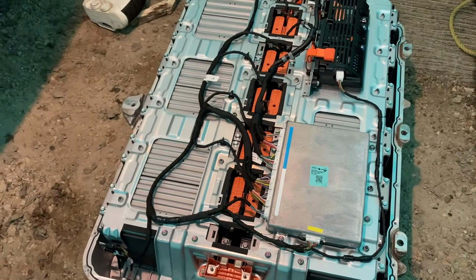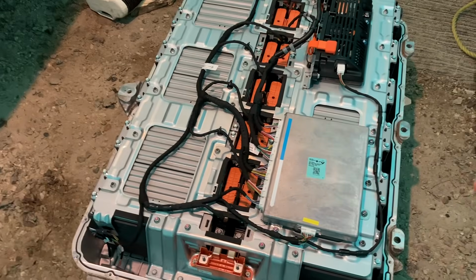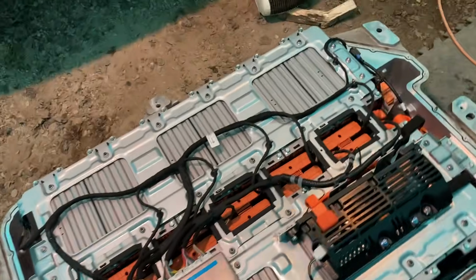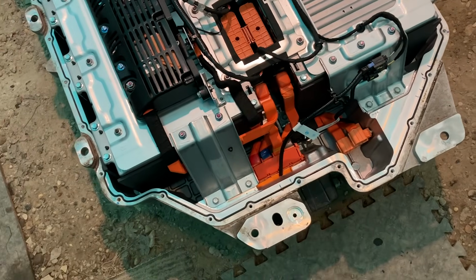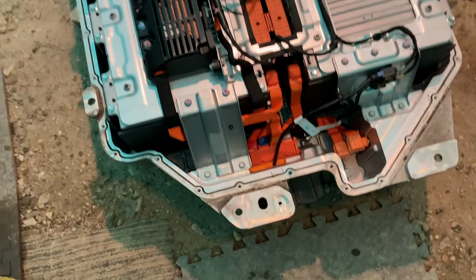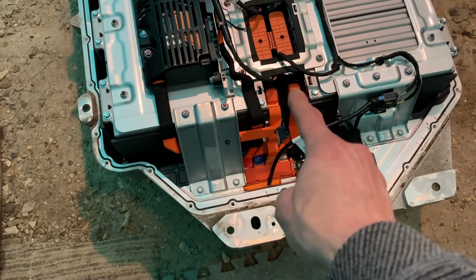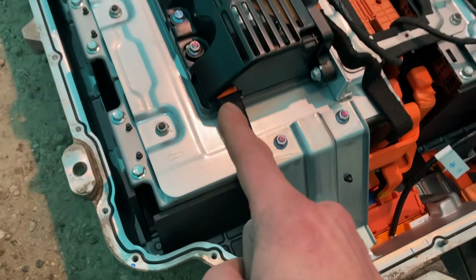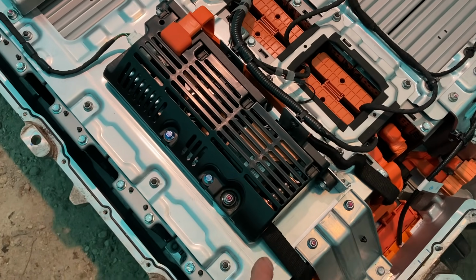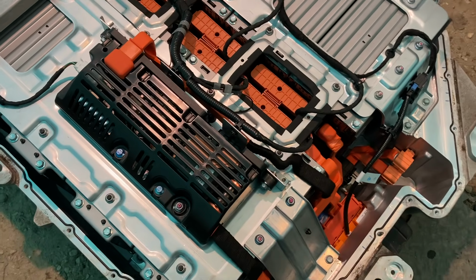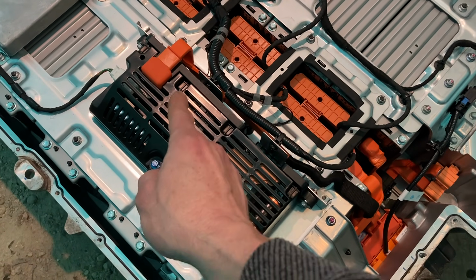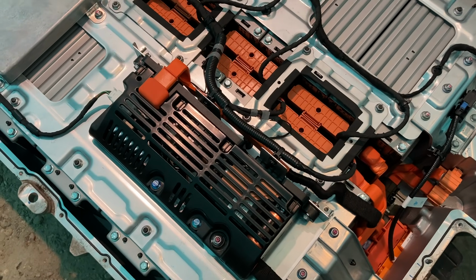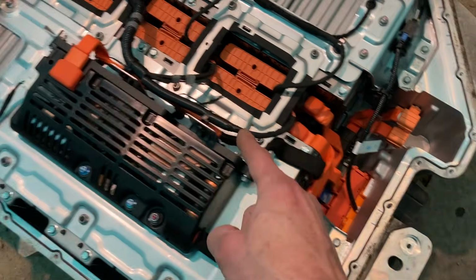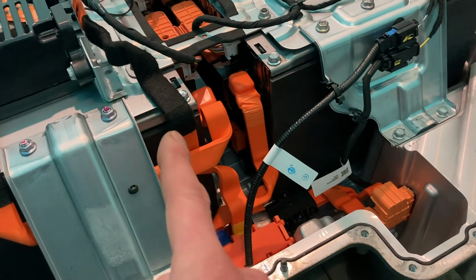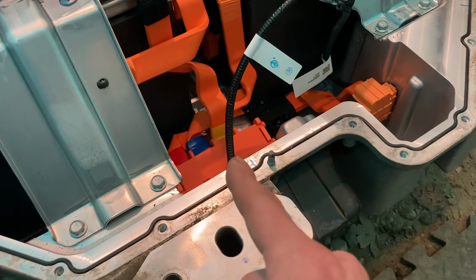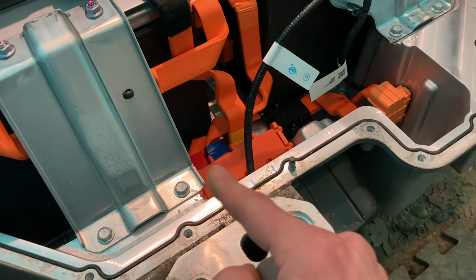So we've got high voltage, but we've chopped it in half. Other batteries have the pull-out fuse in the middle of the pack to achieve the same thing. With these, the fuse is there basically, and it takes out positive and negative. So all our cells connect to here. This busbar, which is a wrapped up busbar, goes into this box, which has the fuse and contactors. So when you start the van you get some clicks and it turns on - these are the contactors, big fat relays basically, and it goes through a warm-up phase called pre-charging, and then it comes on.